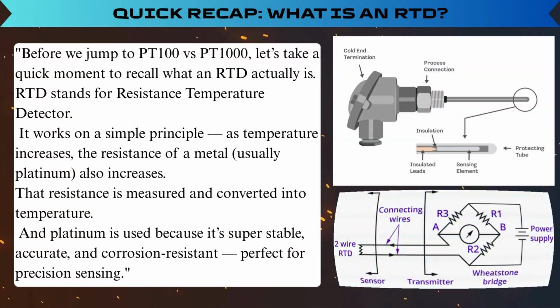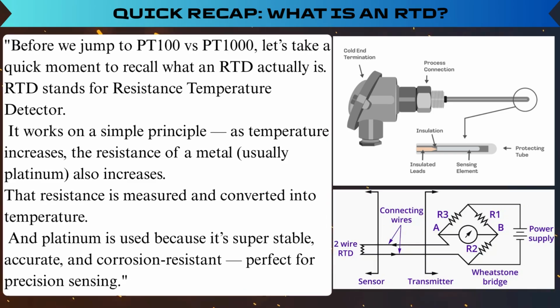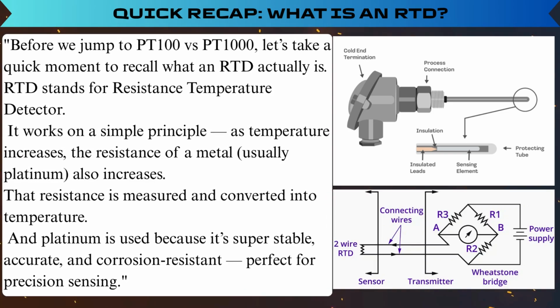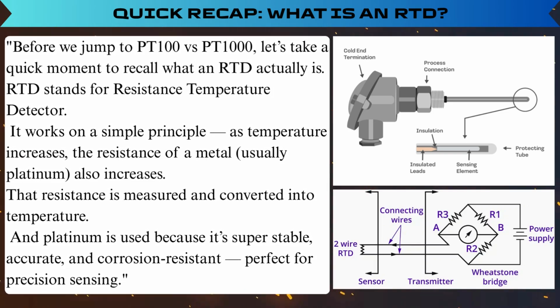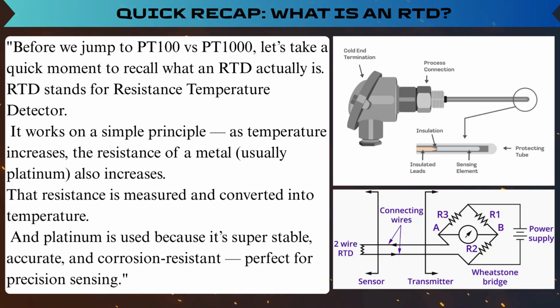Quick recap. What is an RTD? Before we jump to PT100 versus PT1000, let's take a quick moment to recall what an RTD actually is. RTD stands for Resistance Temperature Detector. It works on a simple principle. As temperature increases, the resistance of a metal, usually platinum, also increases. That resistance is measured and converted into temperature. And platinum is used because it's super stable, accurate, and corrosion resistant, perfect for precision sensing.